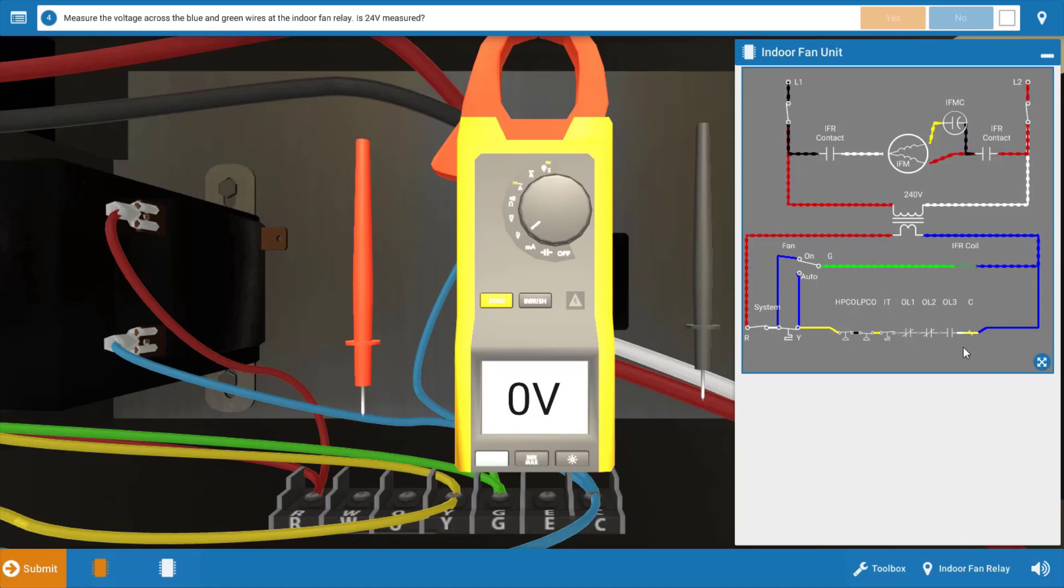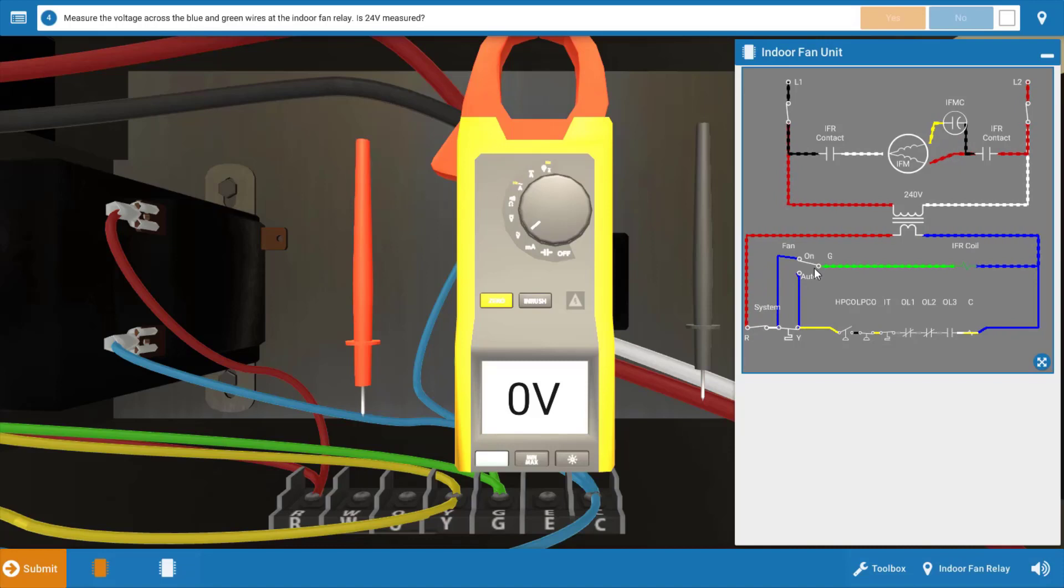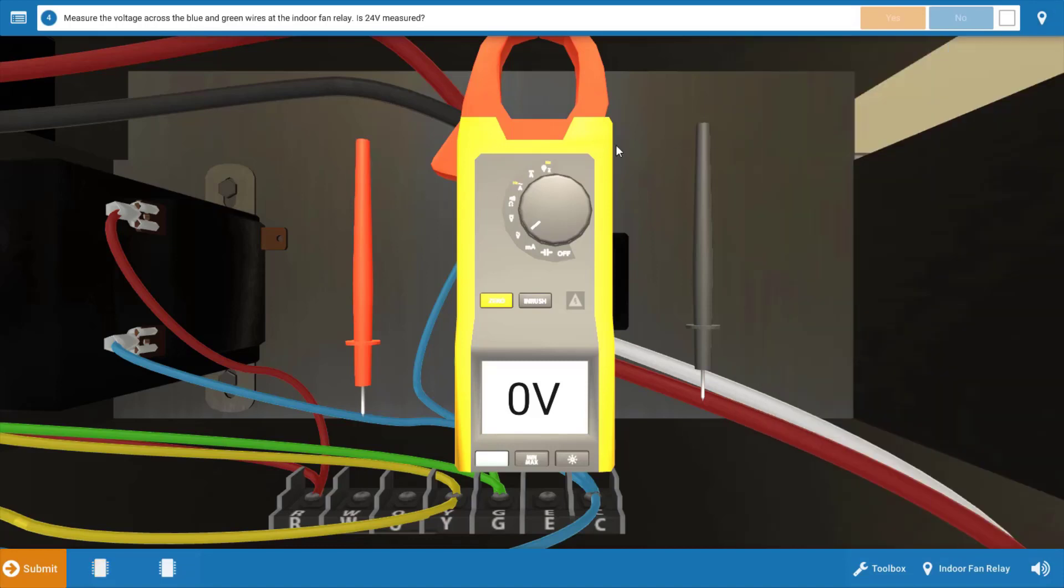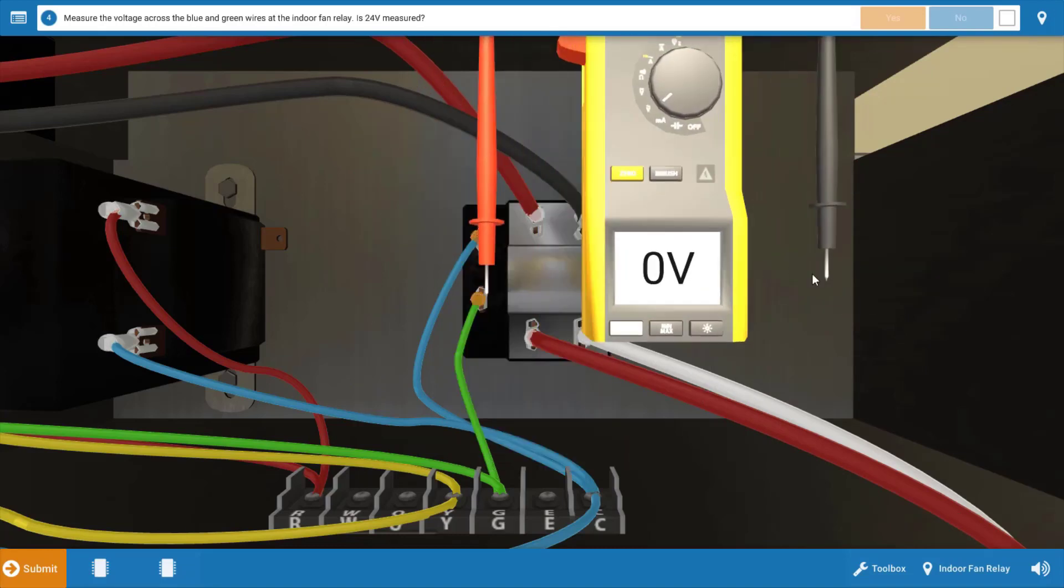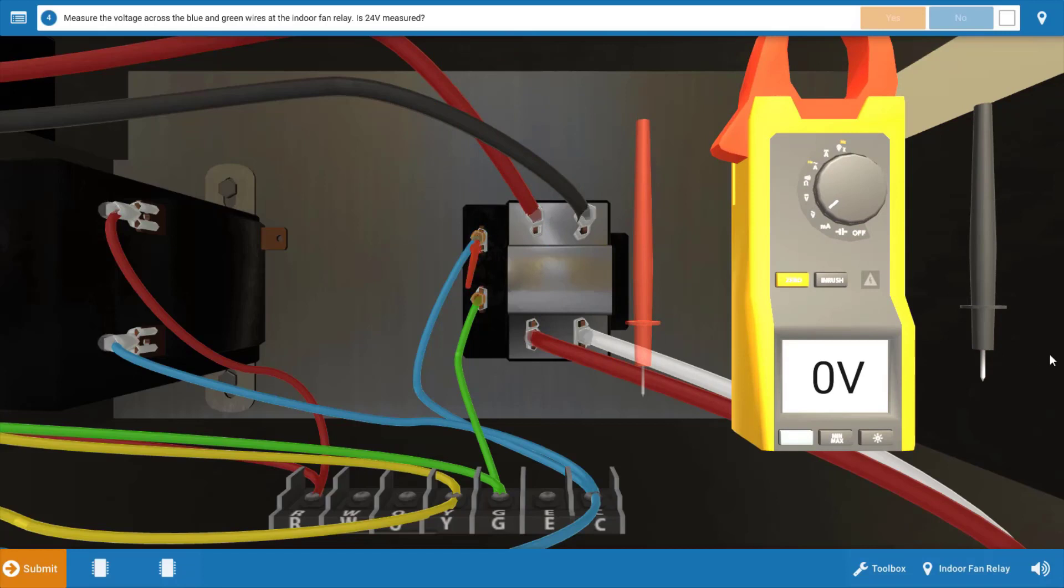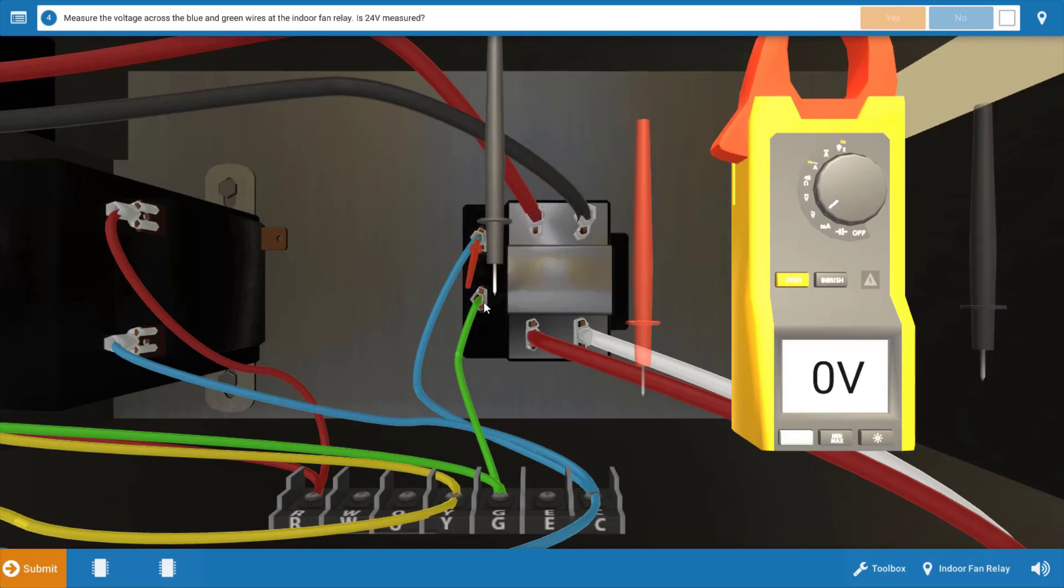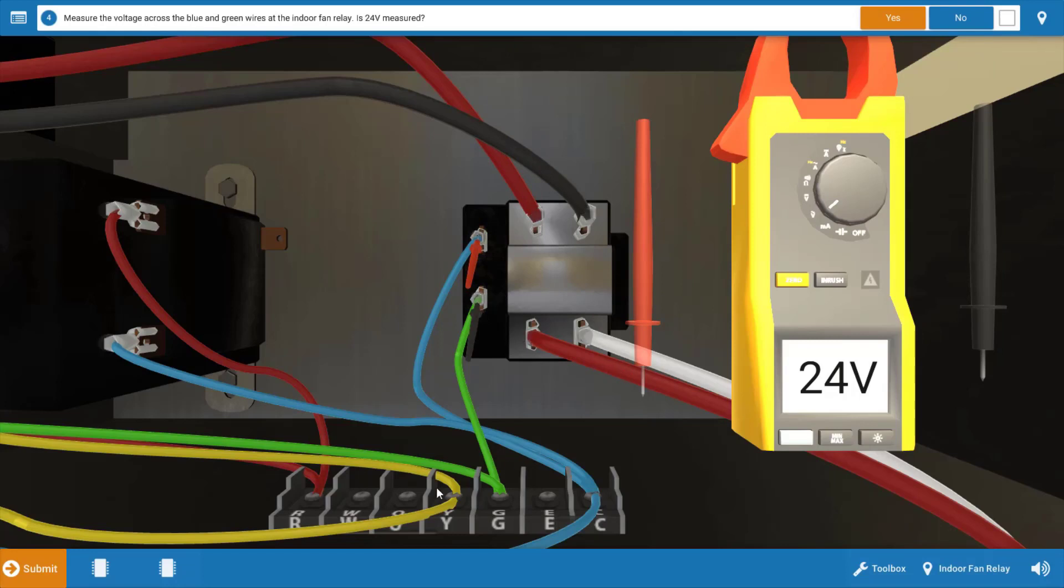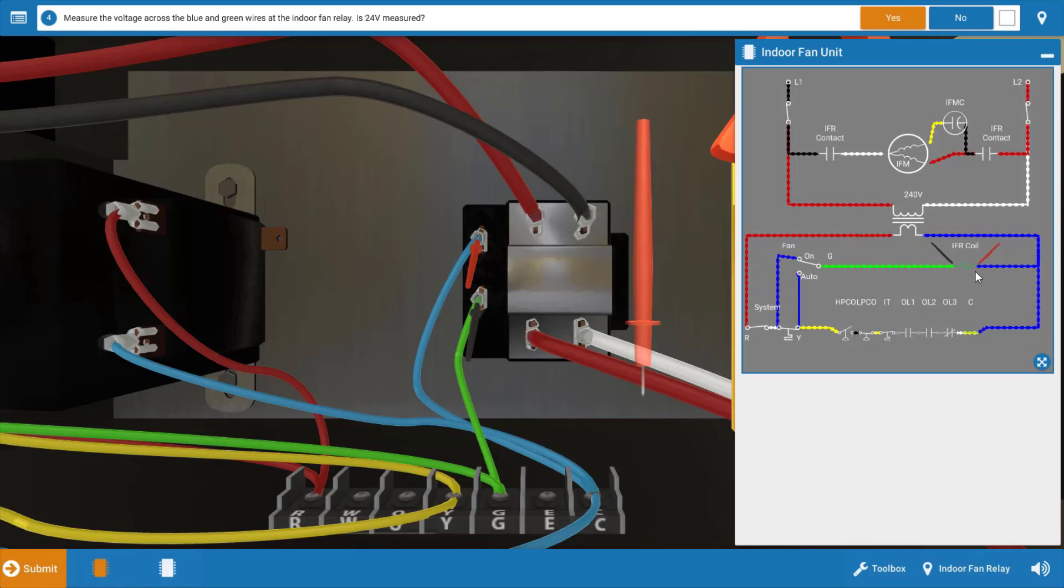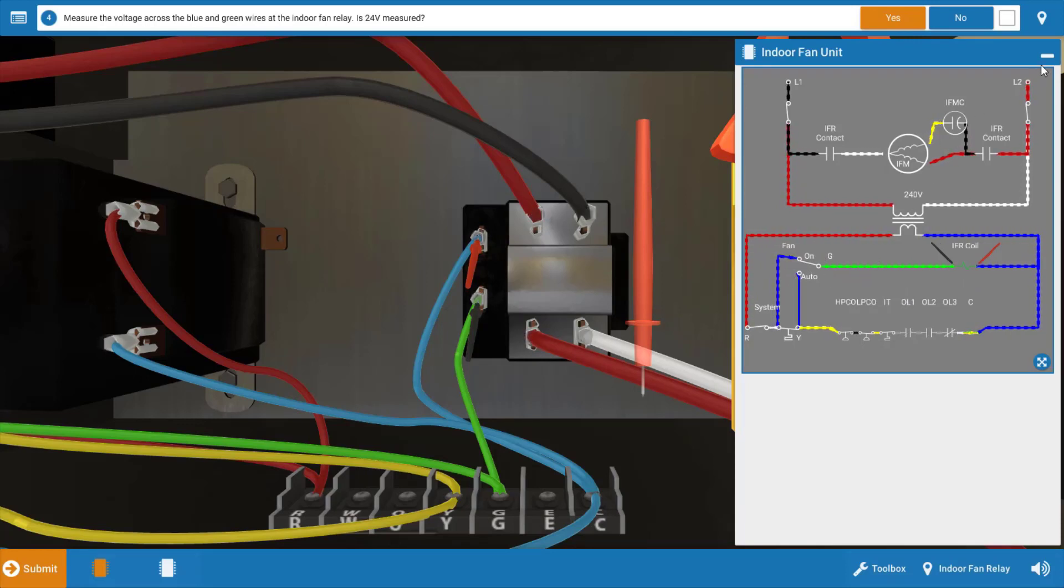Now that we're armed with these four possibilities - the indoor fan motor, the indoor fan motor capacitor, the indoor fan relay, or the thermostat fan switch - we're going to take some voltage checks. To begin with, we're going to place our leads at the indoor fan relay coil and see if we're getting 24 volts to that coil. When we place the leads at the glowing orange hotspot, we can see we do in fact have 24 volts there. We can see the placement of our leads on the diagram. We're verifying 24 volts at the coil. So this eliminates the fan switch within the thermostat as a possible malfunction.